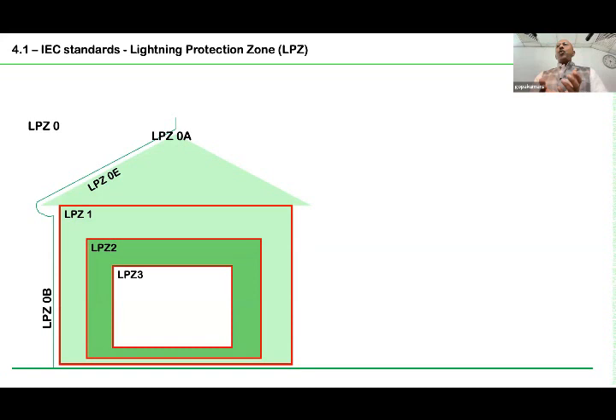within a protected zone, the conducted and radiated energy has to be limited. To limit radiated energy, we have to have shielding. Shielding in the sense of metal, if you are going for, let's say, a defense installation with very sensitive electronics, or a very sensitive communication installation. For those kinds of applications, you have to make a Faraday cage, and your electronics shall be inside the Faraday cage. Then only your devices are protected against a radiated effect.